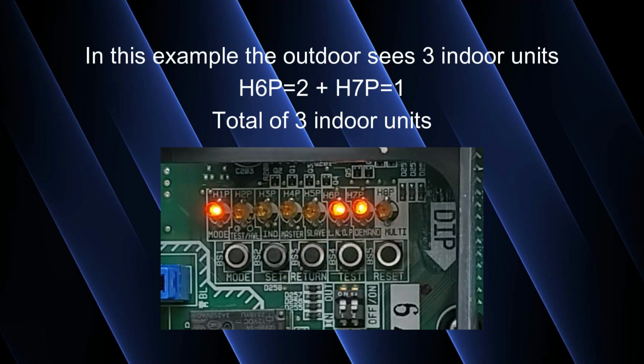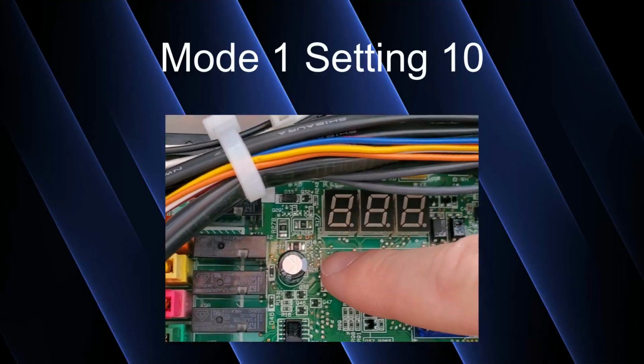If I installed 7, but only lights H5P and H6P were on, that would tell me that that's 6. That means that we are missing an indoor unit, and I'll talk about how to find that missing unit here in just a brief moment. We're going to push pause on the old board. Now we're going to go to the newer style boards that have the digital readout, because in these boards, you need to go to monitor mode 1, setting number 10.